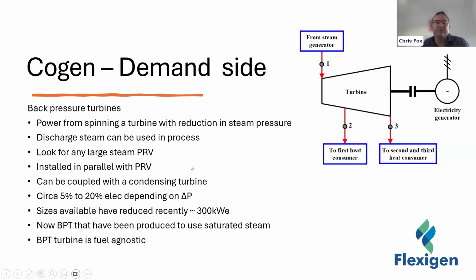Another really interesting thing is they can be quite easily coupled with a condensing turbine, which is the power station thing I mentioned earlier. They literally just put the condensing turbine on one side of the shaft and the back pressure turbine on the other side of the shaft, and both of them feed the generator. So single shaft, one generator. And again, that just gives you incredible flexibility in terms of how much electricity and how much process steam you want out of the system. So if you only want electricity, everything goes through the condensing turbine. If you want a mixture of both, then your control valves will just figure out what's the best balance to suit the load of the plant.